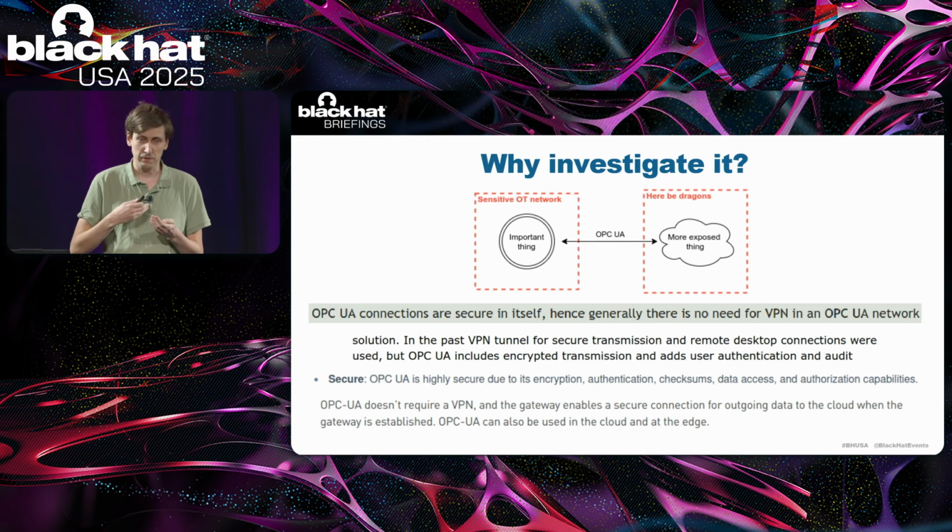And when you do use the client and server authentication features, the trust model is based on certificates. Typically, in many implementations, when a client connects to a server, the first time the connection will be rejected because the certificate is untrusted, and then an administrator on the server side can look at a list of rejected certificates and indicate that they actually do want to trust the certificate. So kind of a pretty pragmatic trust on first use solution. But there's also different setups based on PKIs or just full pre-configuration available as well.